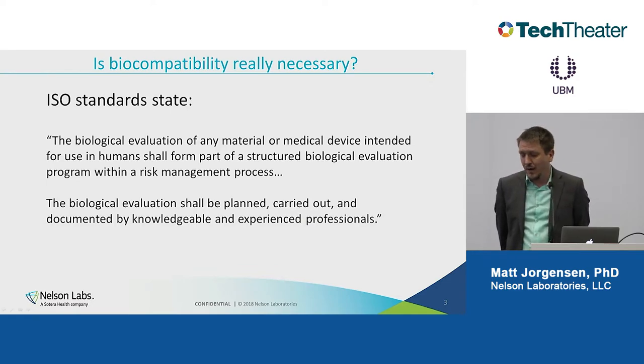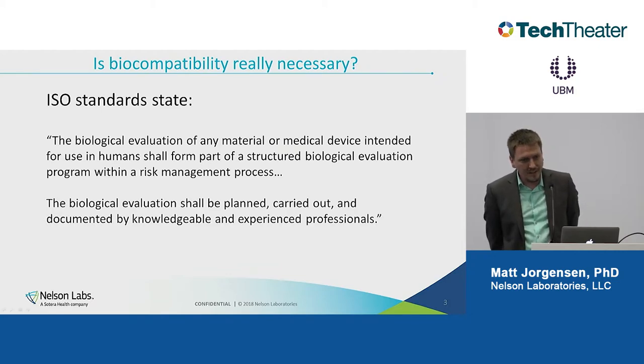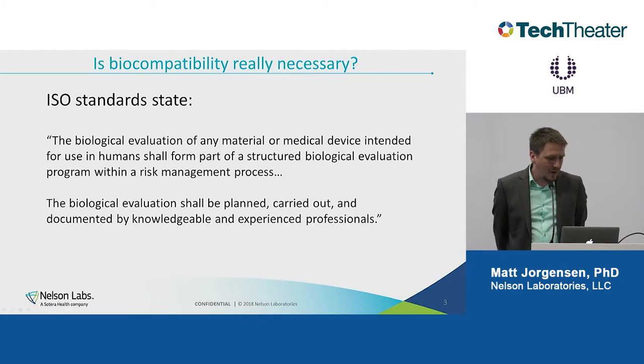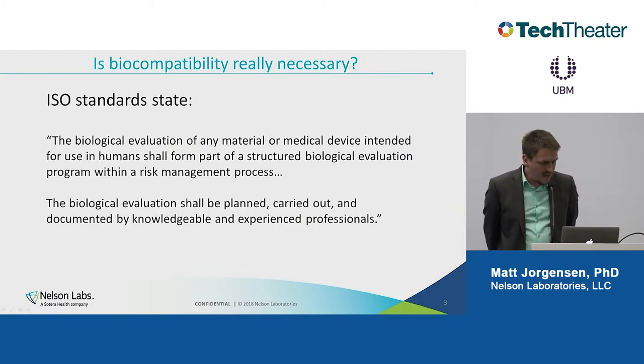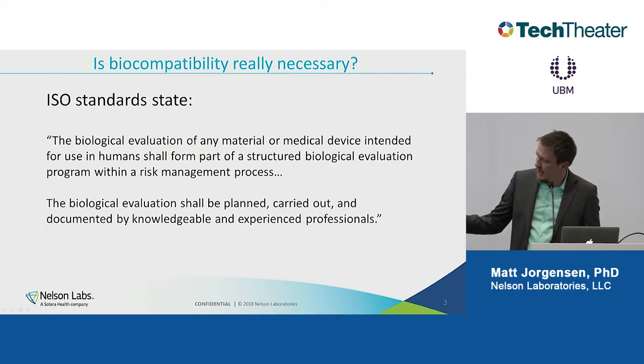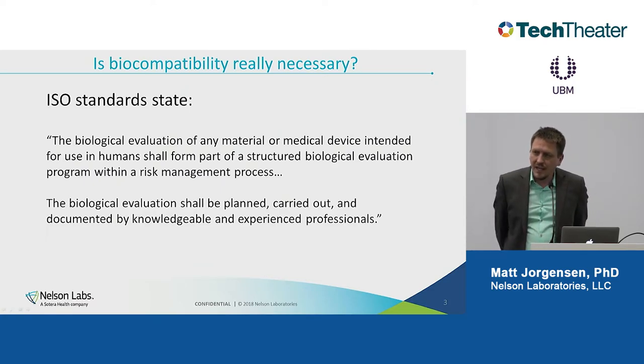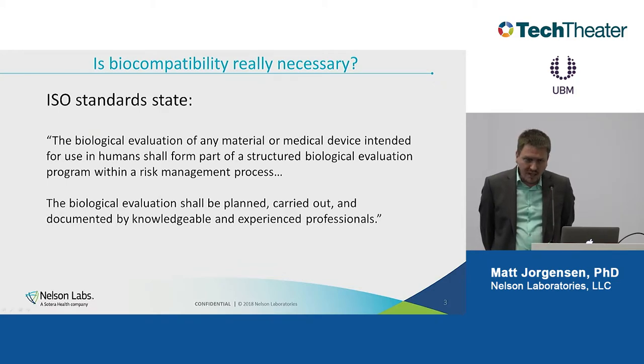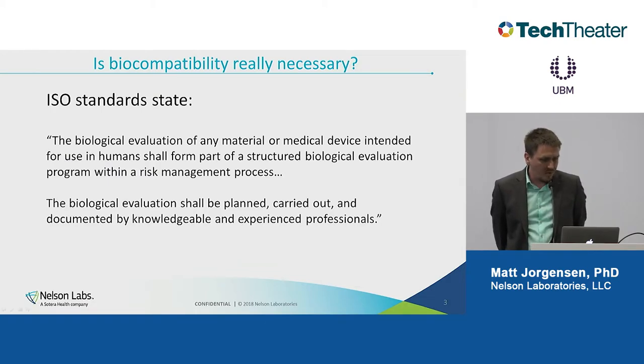We see this too, where a manufacturer might submit to the FDA without doing any biocompatibility testing, and the FDA rejects it and says please do biocompatibility, and then they come to us. It's absolutely clear in the ISO standard that the biological evaluation of any material or medical device intended for use in humans needs to be part of a structured biological evaluation program, and this should be well documented by knowledgeable and experienced professionals.